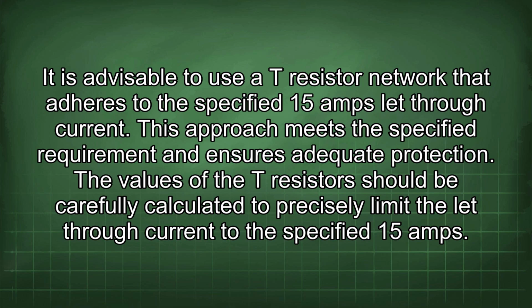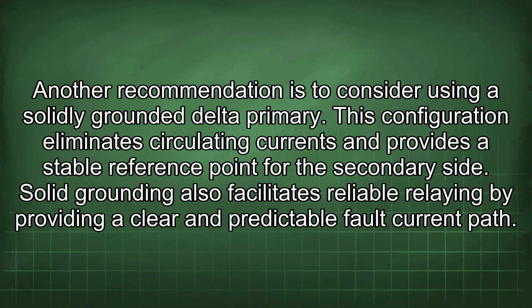The values of the T resistors should be carefully calculated to precisely limit the let-through current to the specified 15 amps. Another recommendation is to consider using a solidly grounded delta primary. This configuration eliminates circulating currents and provides a stable reference point for the secondary side. Solid grounding also facilitates reliable relaying by providing a clear and predictable fault current path.